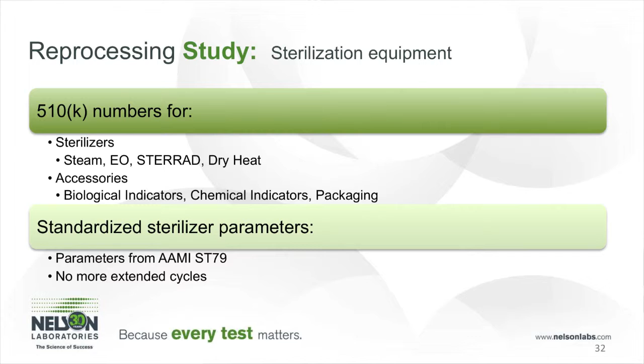For the reprocessing study, we want to ensure that every part of the study has a 510(k) approval. So this includes all the sterilizers, all the biological indicators. The sterilizer specific cycles that we're utilizing need to have 510(k) instructions for all of those, as well as the packaging. We want to ensure that every type of packaging that is utilized has a 510(k) for the specific cycle that we are performing.